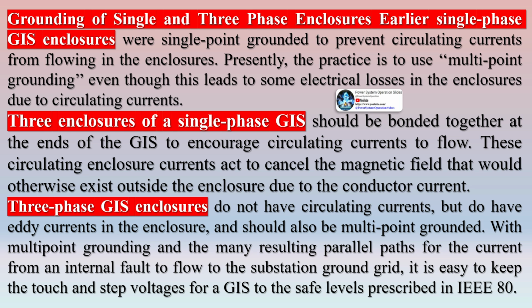Earlier single-phase GIS enclosures were single-point grounded to prevent circulating currents from flowing in the enclosures. Presently, the practice is to use multi-point grounding even though this leads to some electrical losses in the enclosures due to circulating currents. 3 enclosures of a single-phase GIS should be bonded together at the ends of the GIS to encourage circulating currents to flow. These circulating enclosure currents act to cancel the magnetic field that would otherwise exist outside the enclosure due to the conductor current.